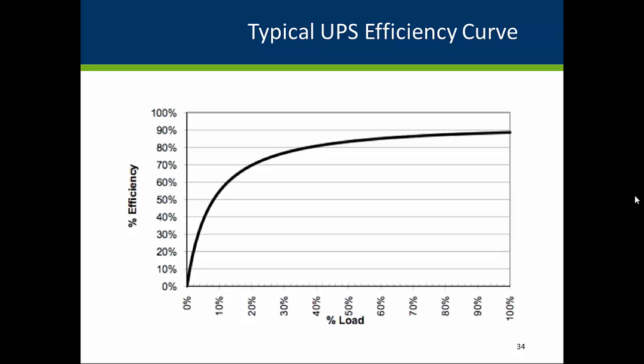All power going to the server racks first goes through the UPS. AC power is converted to DC for the batteries in the UPS, and then converted back to AC as it feeds the PDUs of the server racks. This adds some inefficiency, and as a result, increasing the efficiency of the UPS is an important and appreciable opportunity for savings. This graph shows the efficiency of a typical UPS versus the percent power load on its battery capacity. For this study, the average UPS percent load was about 40%, or about 80% efficiency, with over 50% of the UPSs having a percent load of 40% or less.